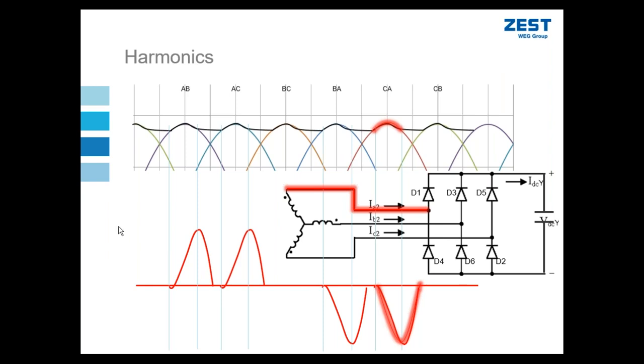But just one interesting thing to note, my capacitor interval, the interval during which my capacitor supplies the energy, is not always the same, even for the same VSD. It is a factor that is determined by the load. By the load, I mean the electric motor. So when the motor is drawing a very light load, my capacitor voltage is very high and drops off slowly. So it stays at a very high level. So my motor spends more of its time drawing energy from the capacitor than it does from the supply.